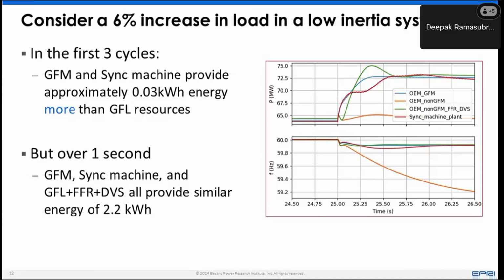As we have more inverter-based resources coming in and start looking at frequency response results, it's important to ask what assumptions are made: the speed of response from an inverter-based resource, how much frequency response it's providing, whether it's even providing frequency response at all, whether it has the capability to do so, how much energy is being injected, and in what time frame. All of these questions have to be answered before determining whether the frequency response of a system is good or bad, depending on the type of inverter-based resource on the system.